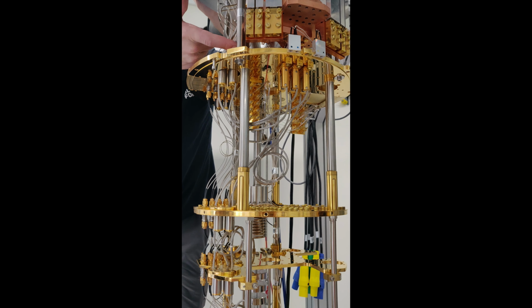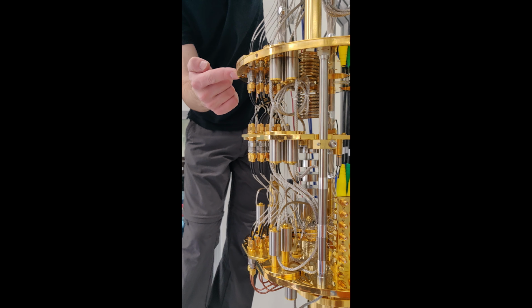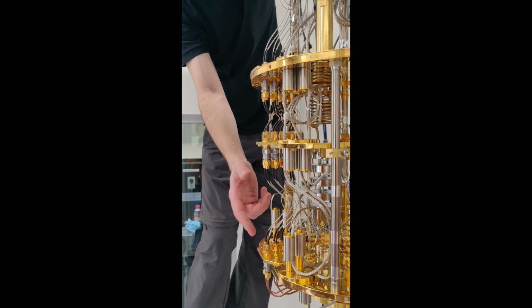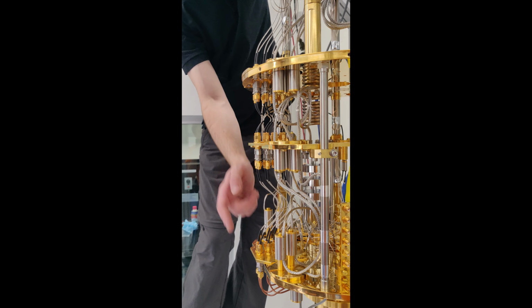there is no gas, no heat conduction, and the heat switch is open. You apply the heater, it conducts. You don't apply the voltage, it doesn't conduct heat. As easy as that. And here we also have heat switches, because again, the mixing chamber will be at room temperature. Like right now it's at room temperature, it will be cooling down to 4 Kelvin as a pulse tube, and then this will be 1 Kelvin, and this will be 10 millikelvin. So we don't need thermal conduction between these.